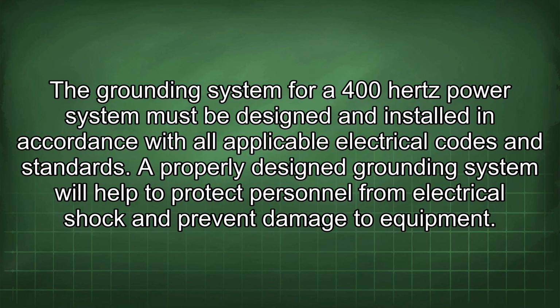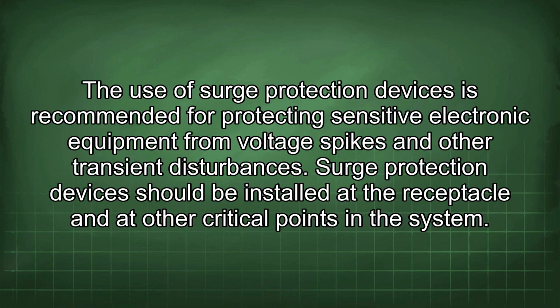The grounding system for a 400 Hz power system must be designed and installed in accordance with all applicable electrical codes and standards. A properly designed grounding system will help to protect personnel from electrical shock and prevent damage to equipment. The use of surge protection devices is recommended for protecting sensitive electronic equipment from voltage spikes and other transient disturbances. Surge protection devices should be installed at the receptacle and at other critical points in the system.